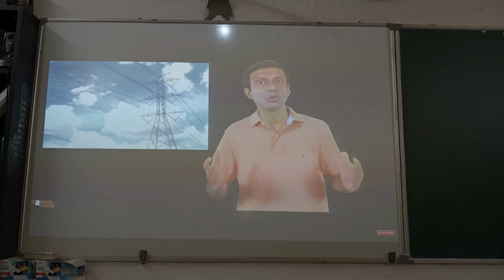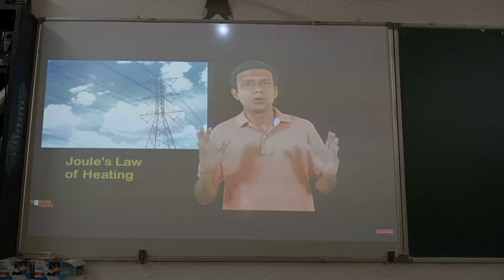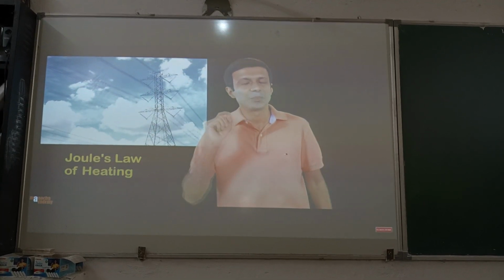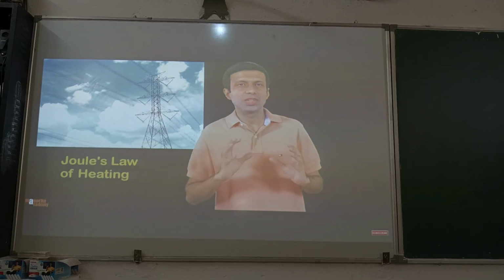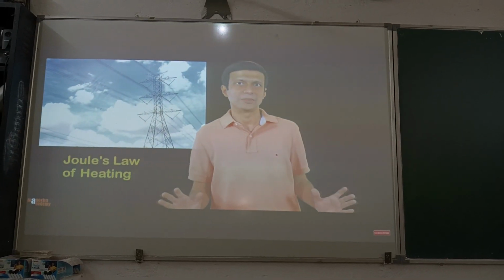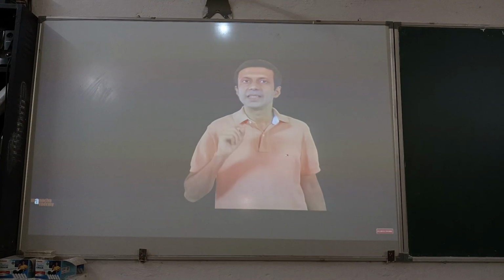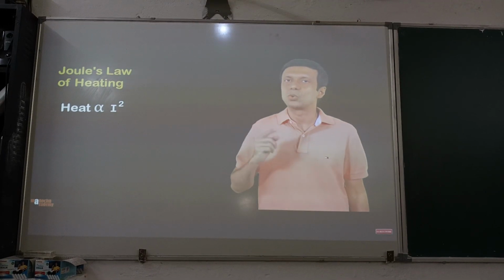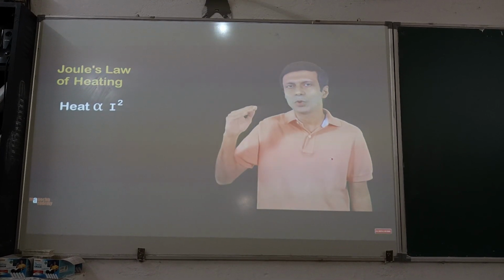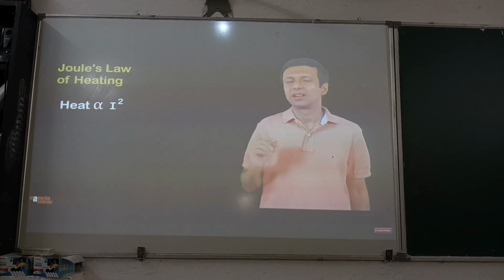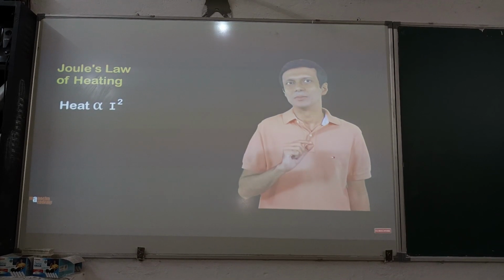That's 11,000 volts. The generated electricity is transmitted from the power station through long electric cables. We know from Joule's law of heating that when current flows in the wires, heat will be produced, so some energy will be lost in the form of heat. The heat loss is directly proportional to the square of the current. So if you want to minimize the heat loss, the current should be very small.